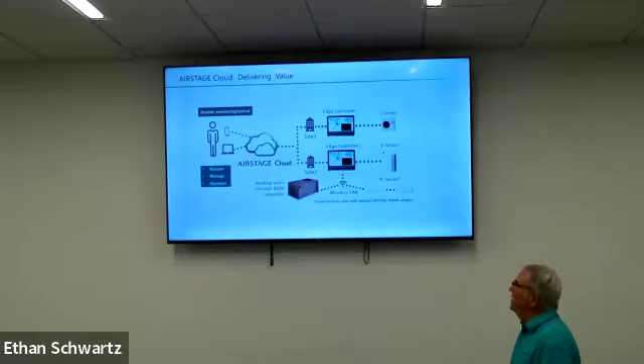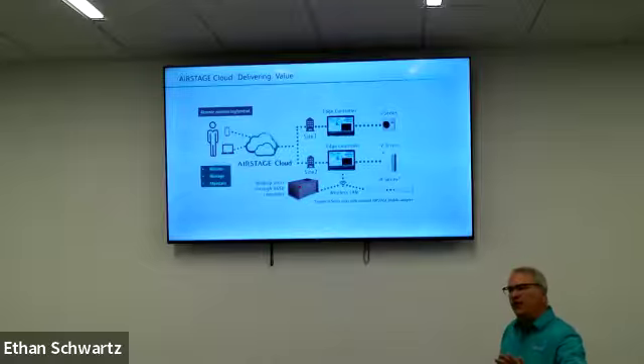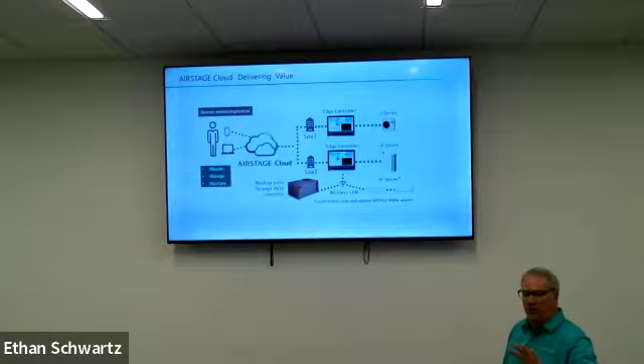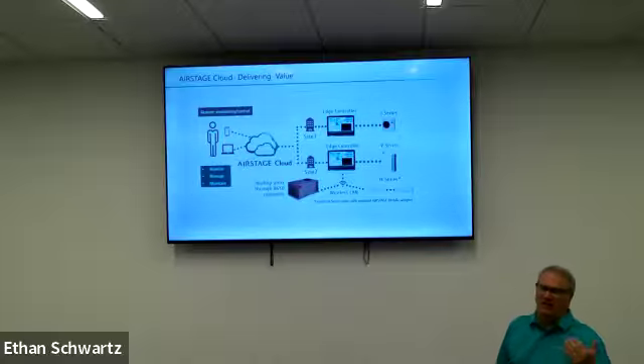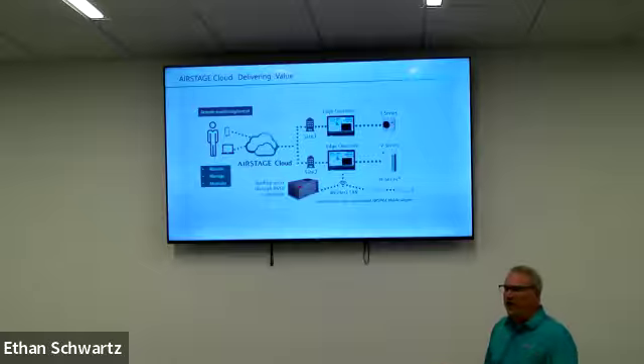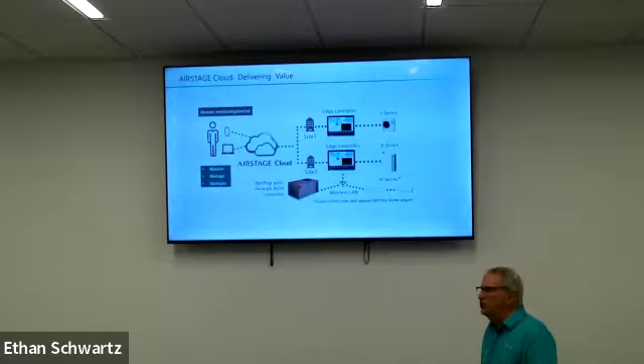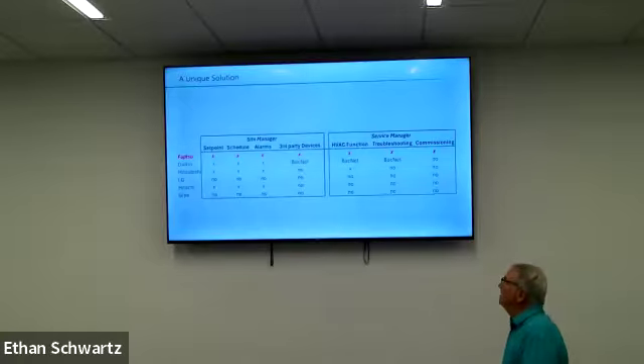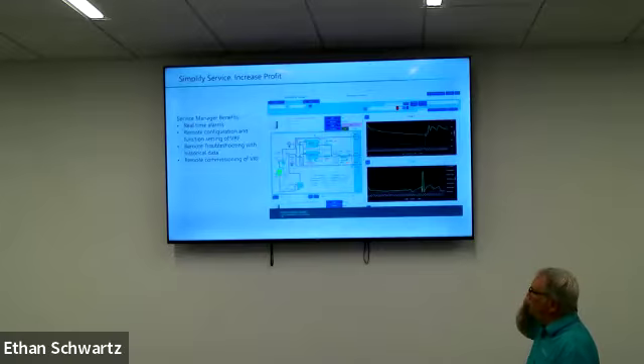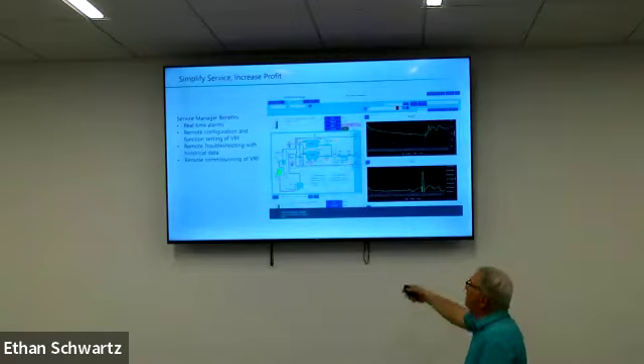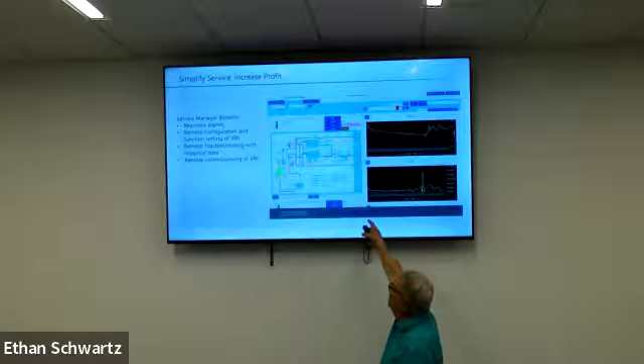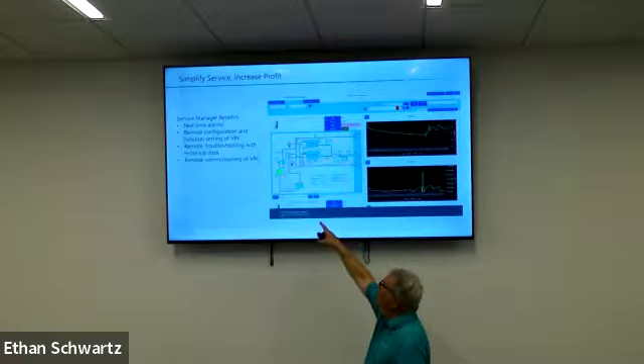I'll show you what this looks like. You can drill down into that customer's building and then drill into their indoor units or outdoor units. On the indoor units, you'd be able to set time schedules, everything as if you were standing there in the building. But it also has the service and diagnostics selection, which is our service tool software. Now, this is a little different view than our actual service software, but it's very, very similar.